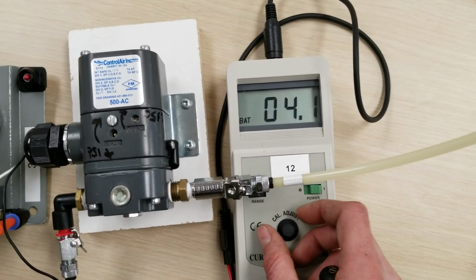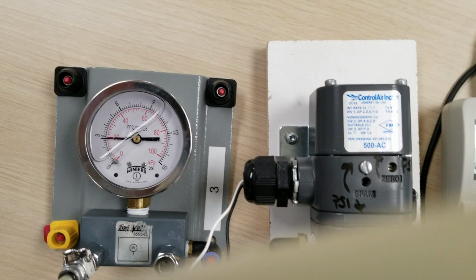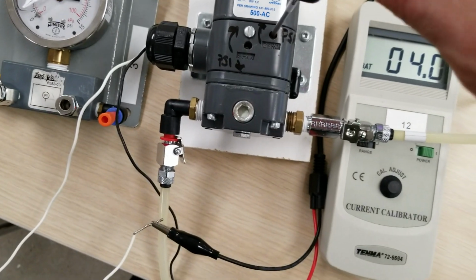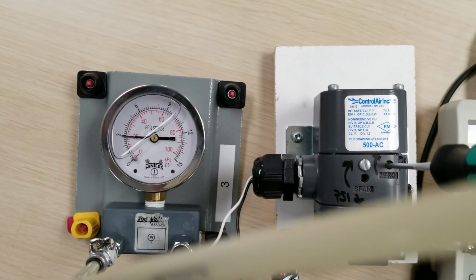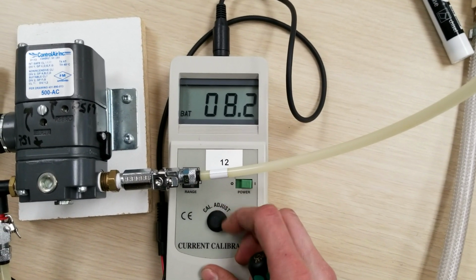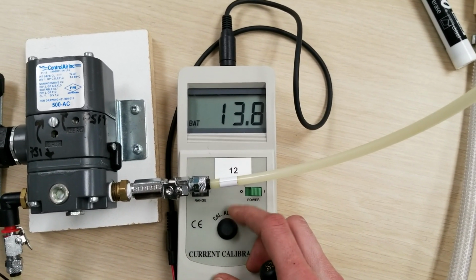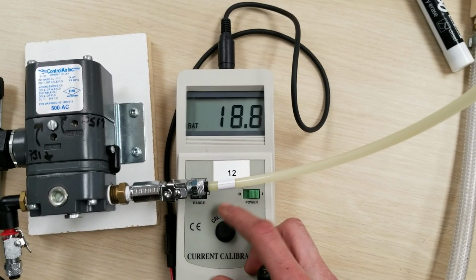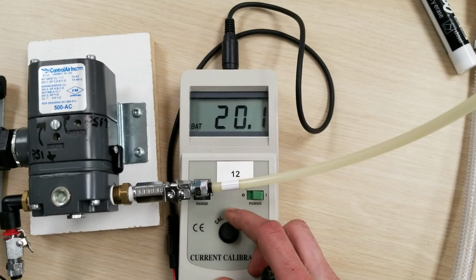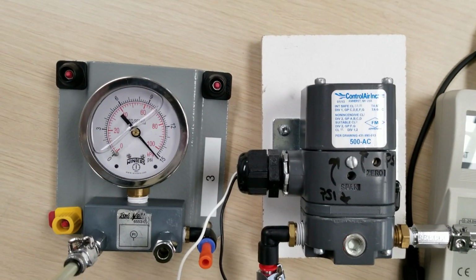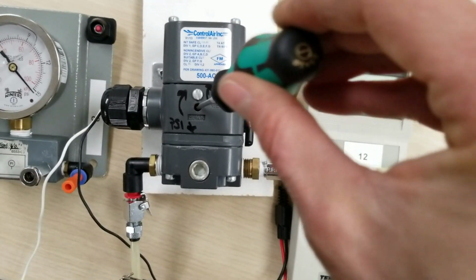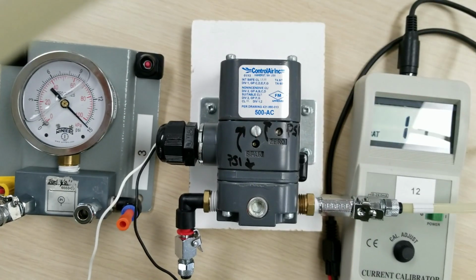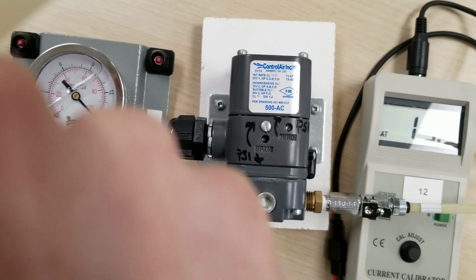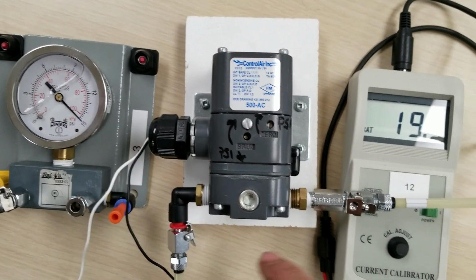Oh, 4 milliamp. Is my zero still okay? Nope, I'll have to adjust my zero again. Then I'll try to adjust my span, or check to see if I need to adjust my span. And I do. There we go. 15 psi. Oh.